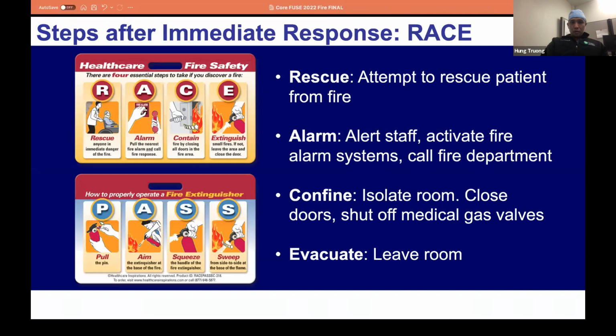What are the steps for immediate response? In the healthcare setting, the acronym is RACE. Rescue: attempt to rescue the patient from the fire. Alarm: alert the staff, the OR team, the fire department, and activate the fire alarm system. Confine: isolate the room, close off the doors, and contain the fire if it persists. Evacuate: leave the room to a safer area.